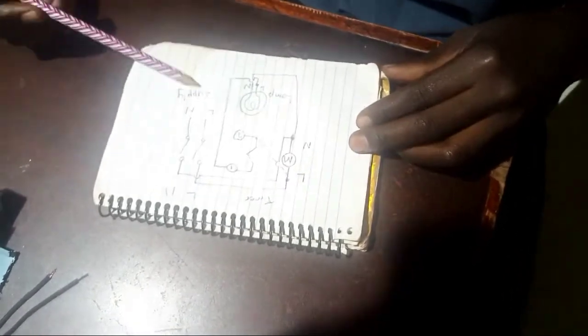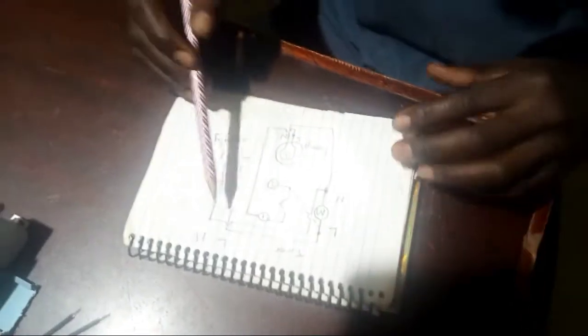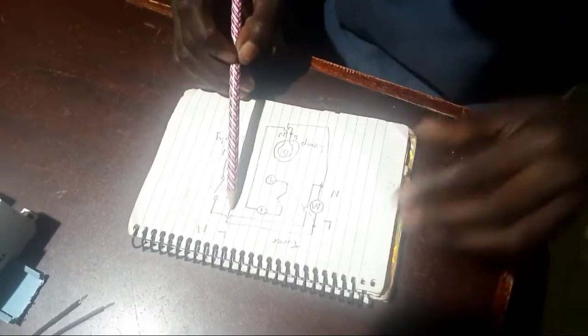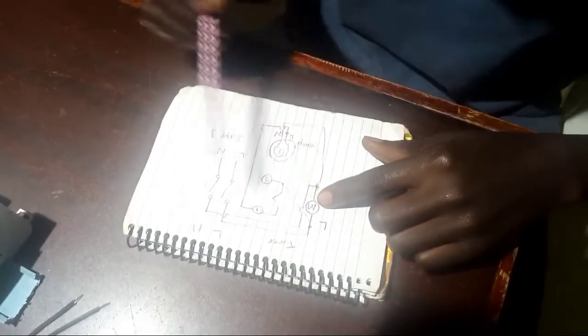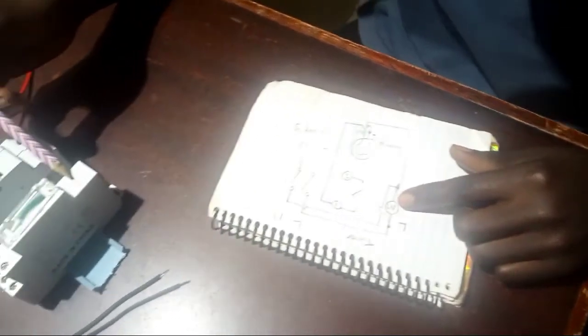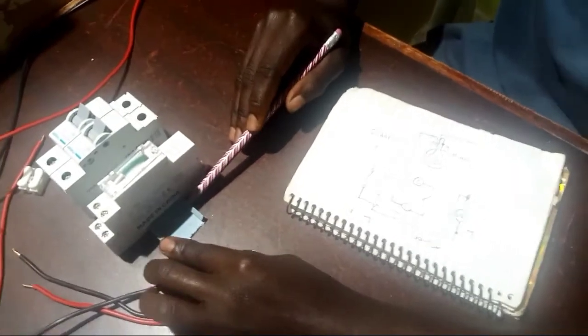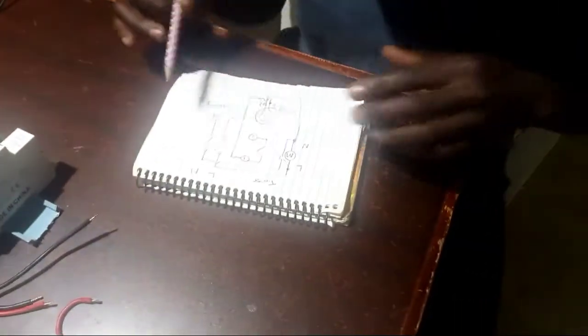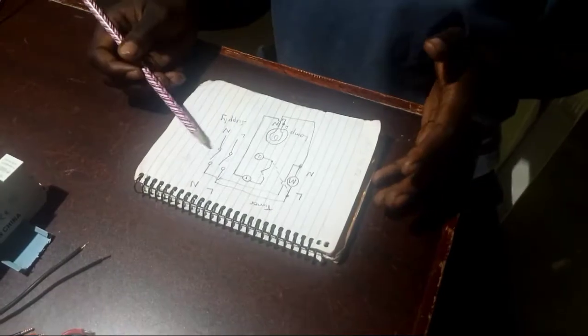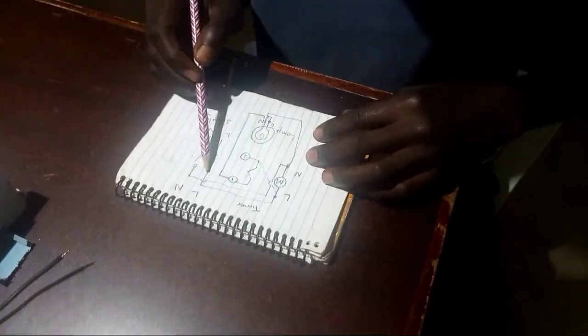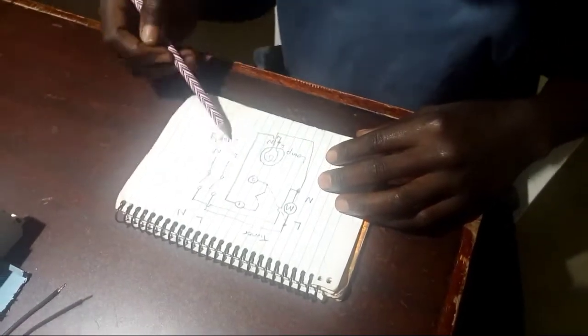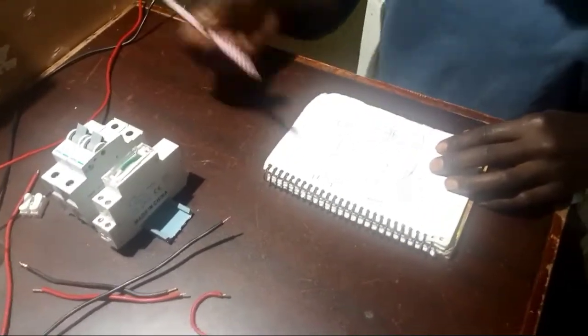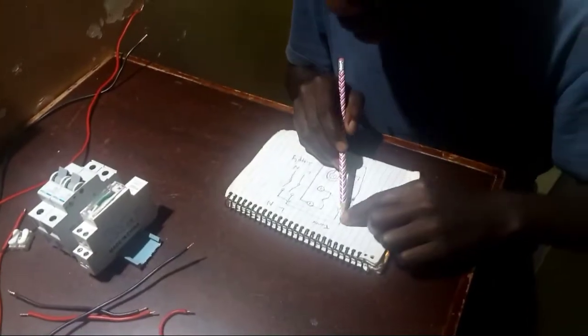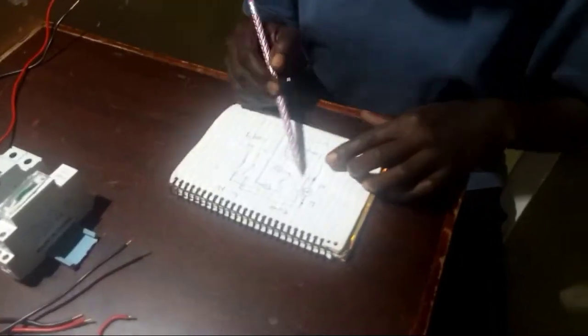The supply is going to come from here to the circuit breaker, and then from the circuit breaker, our live terminal is going to connect with the live terminal of our timer. So this is our timer, and these are our circuit breakers, and the rail they are sitting on is called a DIN rail. On connecting, as you are seeing in our wiring diagram, the live terminal from the power source, the incoming power, goes to the live terminal of the circuit breaker, and the neutral you're going to get from the supply. So a live to the live of the timer, then neutral to the neutral of the timer.